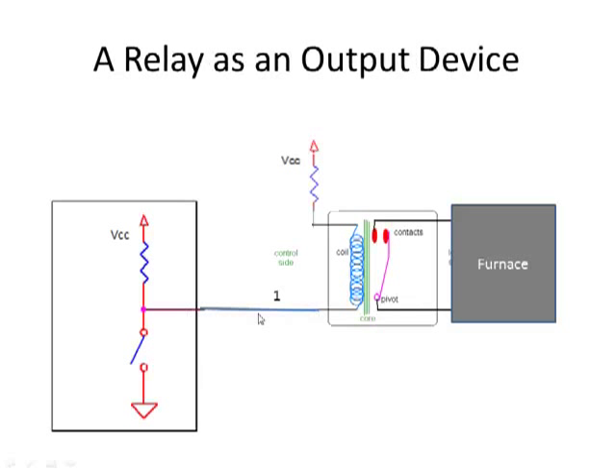Now, that means right here, I've got positive five volts. Well, VCC is positive five volts as well. So if I look at this, is there going to be current flowing through here? I have a path going from VCC on this side to VCC on this side. These are both plus five volts. There's no difference in potential. Therefore, there's no current flowing. This coil is not energized. The electromagnet is not turned on. The arm is not drawn over here, which means the contacts remain open, which means the furnace is off.